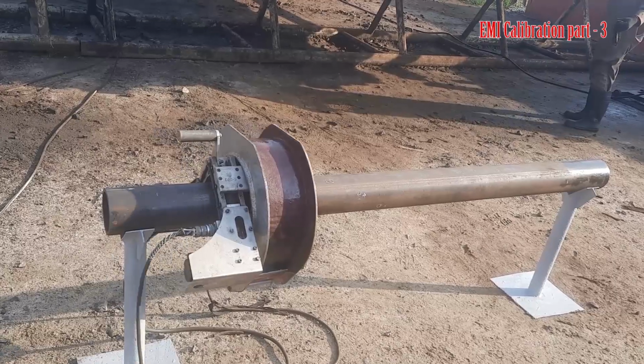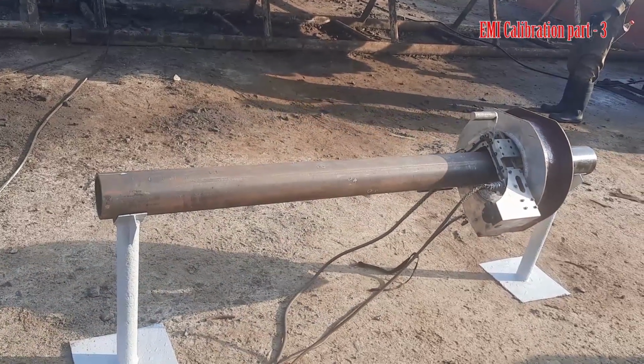If it is not moving, first check the speed. If the speed is 0, the buggy will never move, so increase the speed. If there is still no movement, check the breaker. If the breaker is okay and the buggy speed is high but the buggy is still not moving, you have to check the cable system. That is the buggy troubleshooting technique. Then, to adjust the speed, select the speed at which you can easily run it on the calibration block, and move the buggy forward and backward. Then the buggy is okay. Right now your buggy head, coil and drive are all working, because it can move forward and reverse on the calibration block.